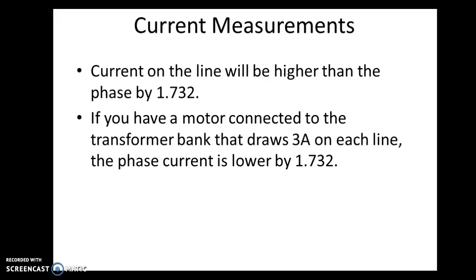Your current measurements: really we can only measure the current coming in on the line. Without being able to put our multimeter around the coils of wire on the transformer, we would then have to calculate how much current we would have on each phase. So if we had, for example, 3 amps on each line coming into the transformer, you would expect to see it lower by 1.732, which actually brings it down to about 1.732 amps.